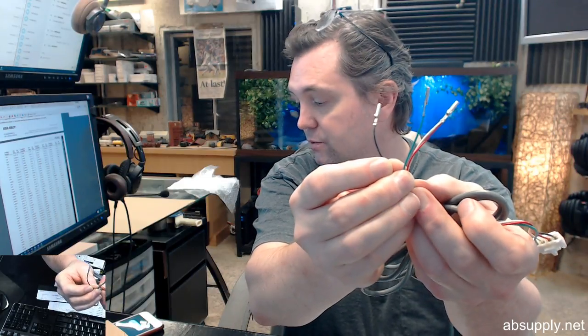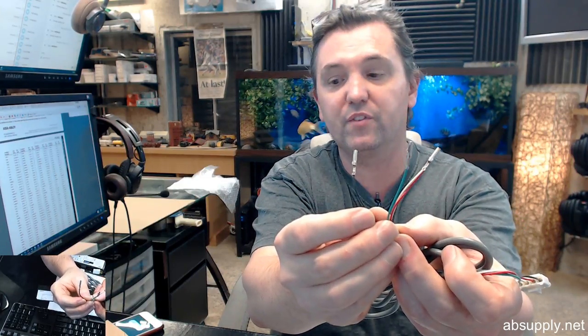There is in figure 4 down below the legend of the wires that correlate to the wires that you see here. So it'll be very simple and straightforward to review. During the 10-second calibration period, there cannot be any movement whatsoever, or it will throw the calibration off. The calibration is intended to give you a baseline from where then you may, if you need to, customize the settings for angle, for sensitivity, things of that nature. So you'll want to establish that baseline.